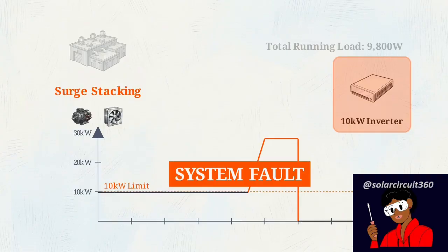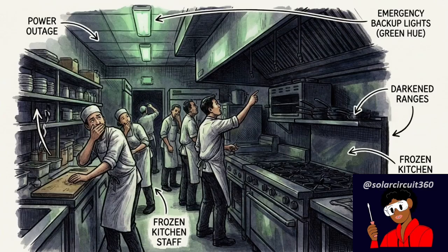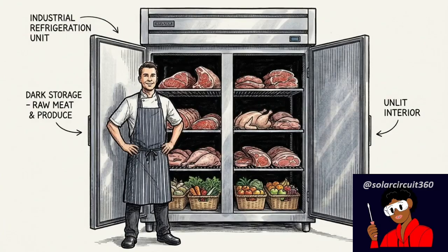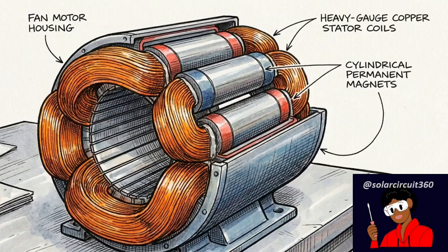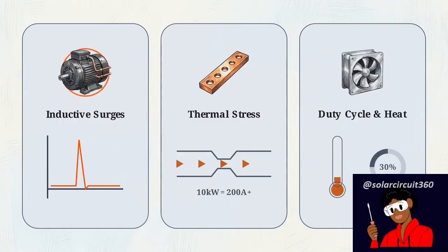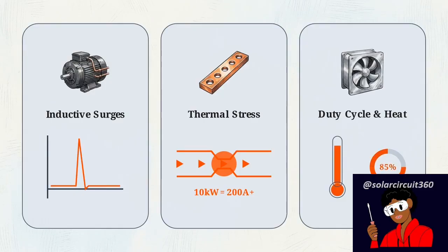The system faults. An unexpected inverter shutdown in the middle of a dinner rush stops refrigeration cold. Inventory spoils, prep lines go dark, and an entire business is forced to close its doors during peak revenue hours. That failure happens because running watts do not account for the specific physics of commercial loads. To build a system that survives, the design must handle inductive surges, high amperage thermal stress, and the way kitchen heat changes how often compressors run.